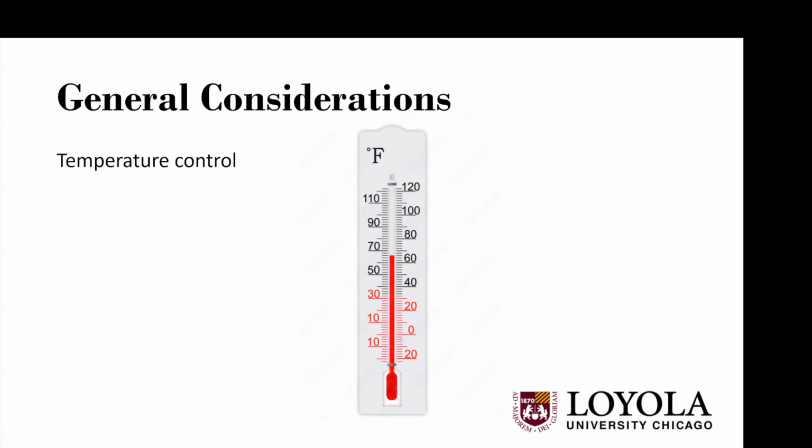But that is usually not possible in the cath lab, because if you do that, the humidity in the air changes, and that could affect the catheterization X-ray equipment, lab equipment, and that may not function if the temperature and humidity are higher, because of the moving parts in the X-ray machine. So you have to adapt to other strategies to be able to keep your patient warm.